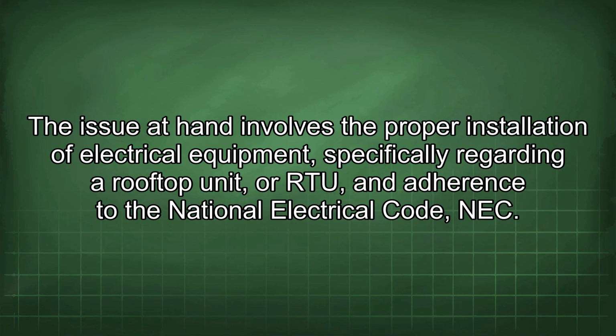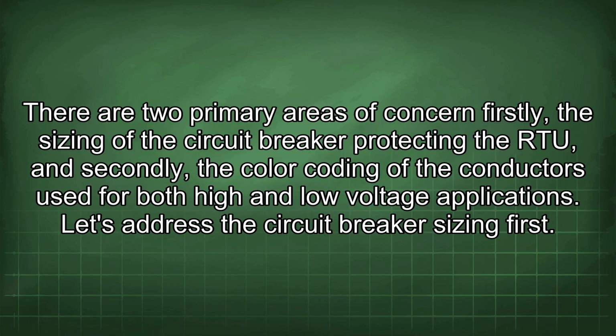The issue at hand involves the proper installation of electrical equipment, specifically regarding a rooftop unit, or RTU, and adherence to the National Electrical Code (NEC). There are two primary areas of concern: firstly, the sizing of the circuit breaker protecting the RTU, and secondly, the color coding of the conductors used for both high and low voltage applications. Let's address the circuit breaker sizing first.